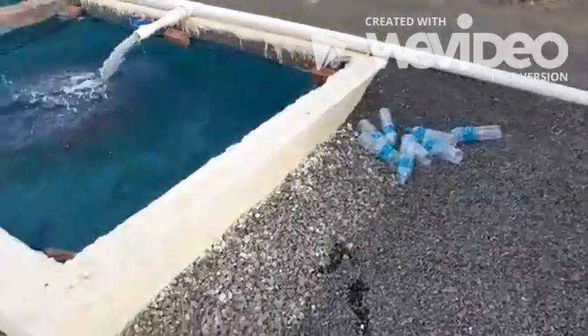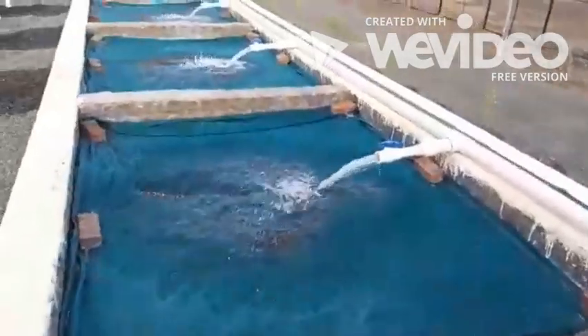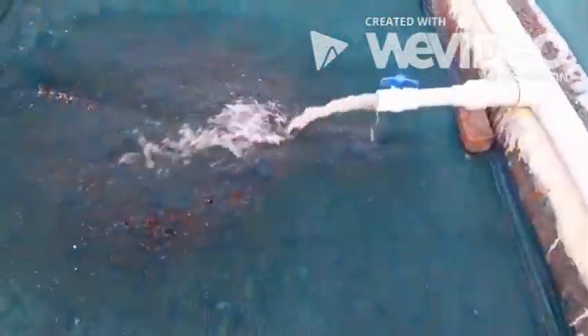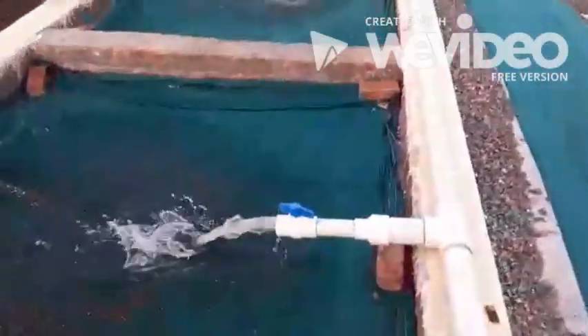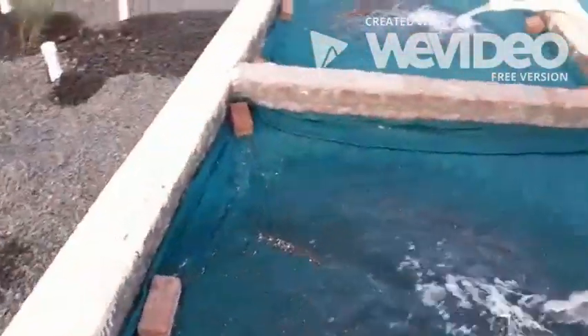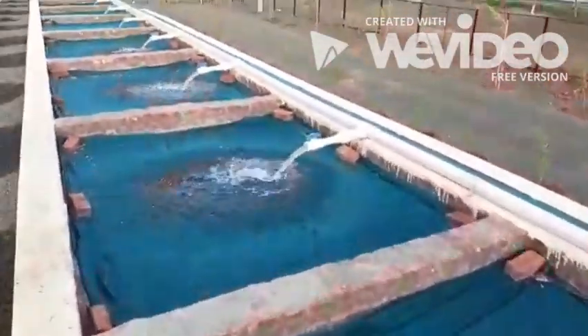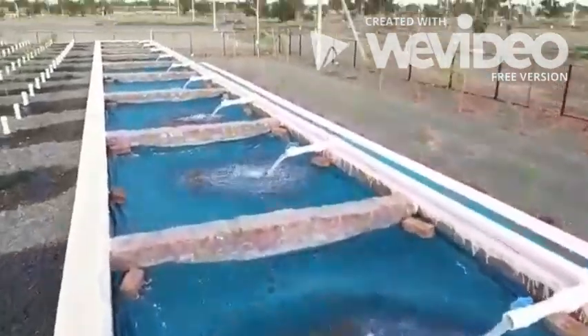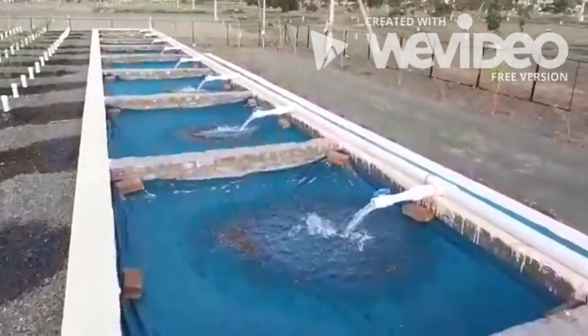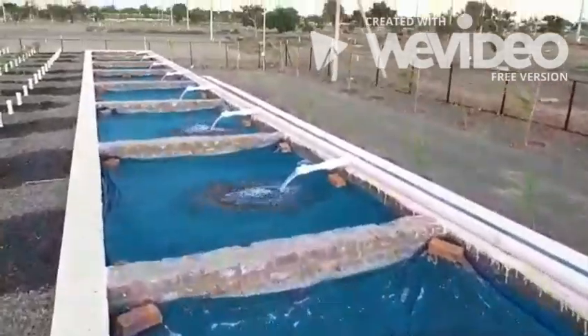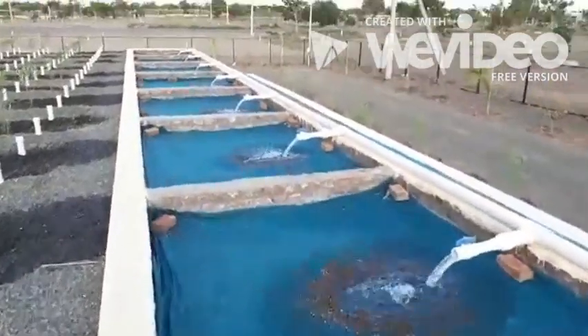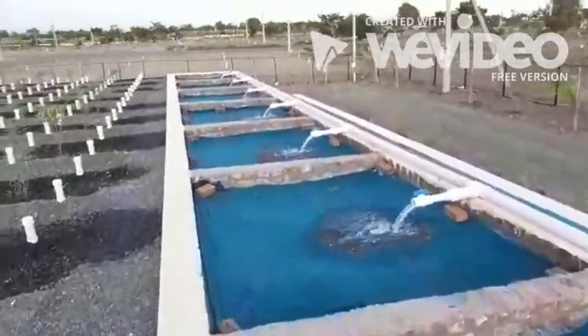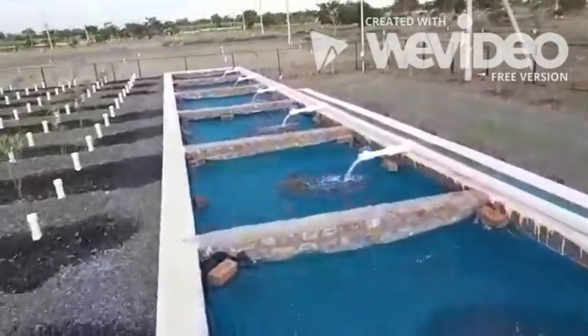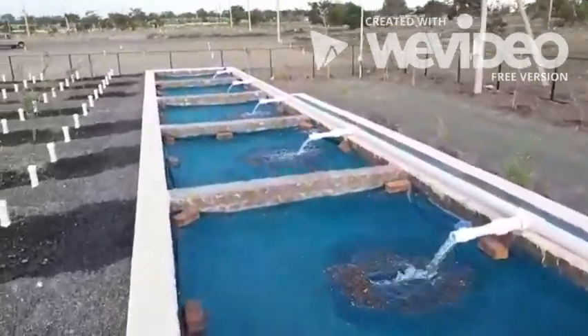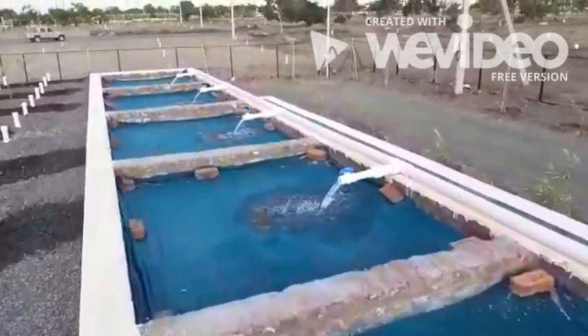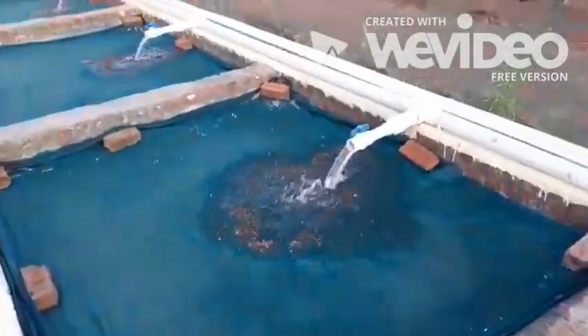The sludge from the bottom of the tube settler is pumped into the solids handling system, which is built on top of the biomound 1 process. As you can see, the sludge is accumulating on top. And once the sludge is dewatered, a red worm culture is used to compost these sewage solids and convert it into vermicompost.